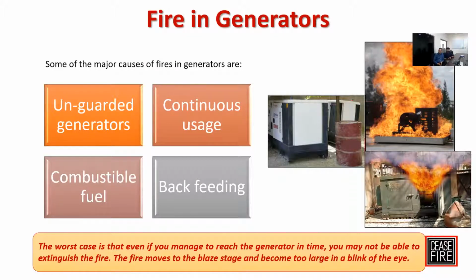But when gensets catch fire, you are out of backup. Second, this fire can grow rapidly because it has fuel - a Class B fire risk is also there. This fire can spread from the genset to adjacent areas and become bigger and bigger. So don't underestimate generators or genset fires.